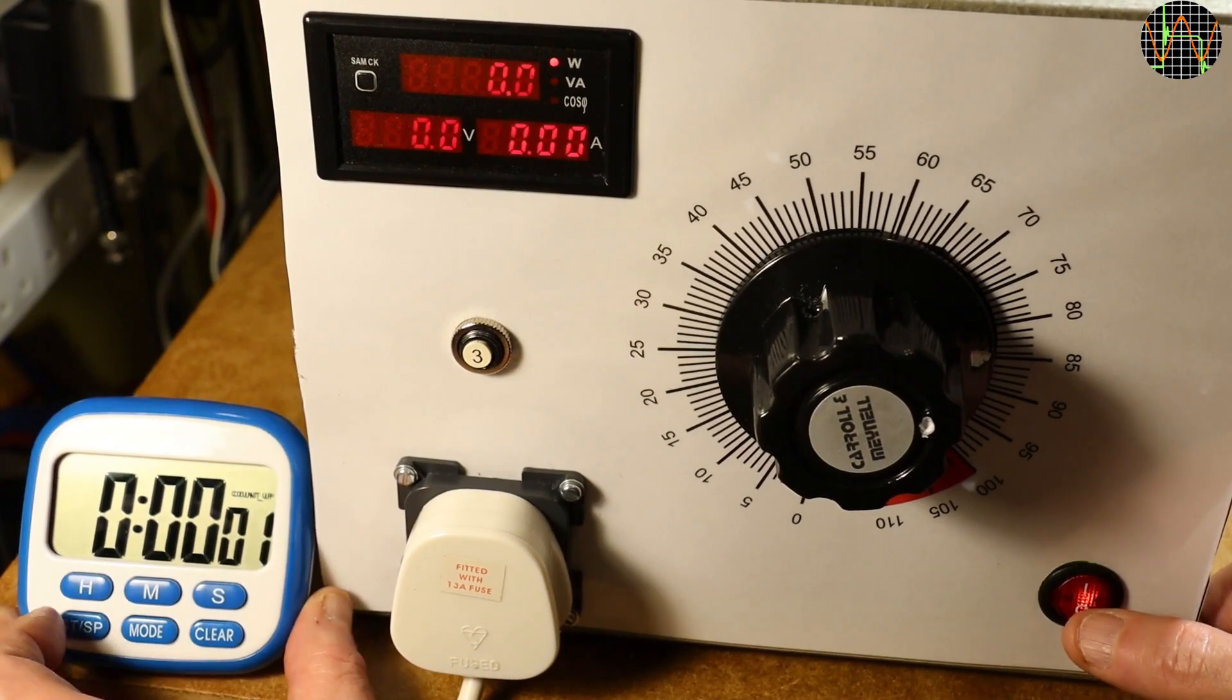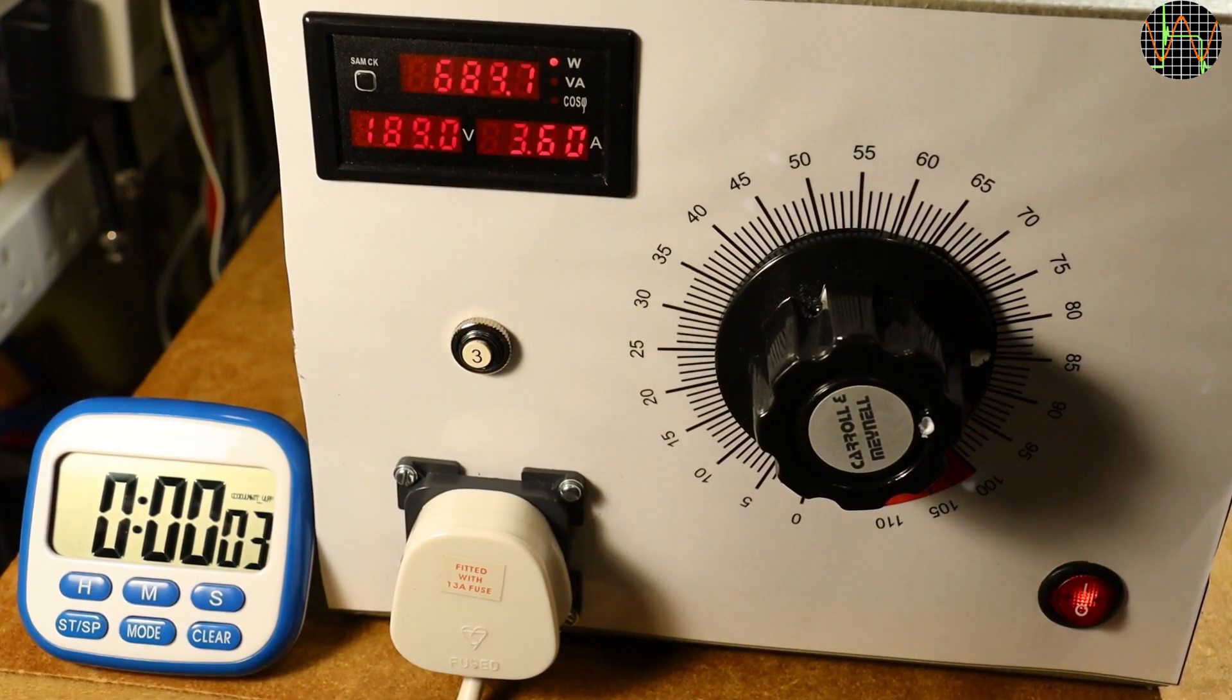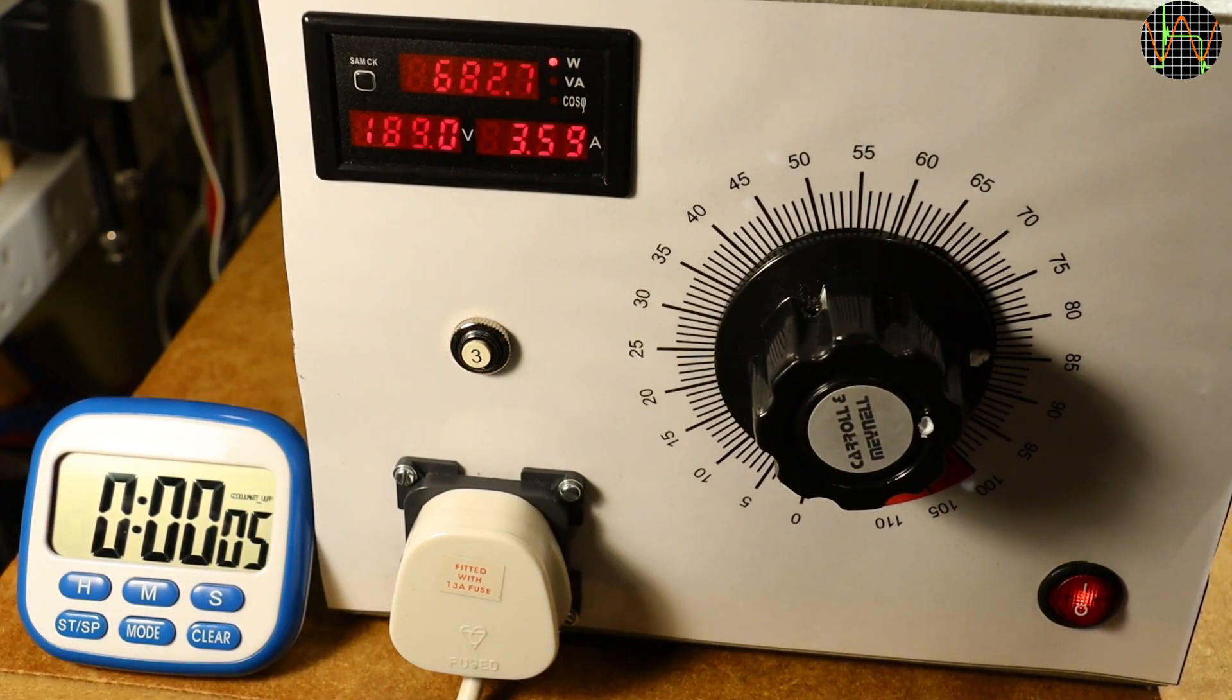As a full load test, I connected the fan heater to the output. That would nominally exceed the rating of the transformer so I reduced the voltage a little to stay just at about the 3.5A mark. This load should eventually trigger the 3A circuit breaker and I am using the stopwatch to test how long that takes.